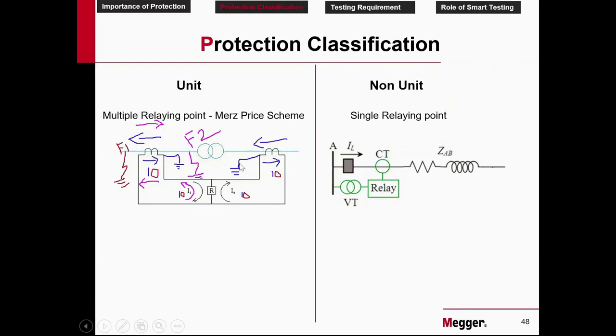Whereas here we have two CTs. This is measuring one current, this is measuring another current. We are subtracting the quantity. So we have multiple relaying points. You can have 3 CTs if it is a 3-winding transformer. You can have 10 CTs or 20 CTs if it is a bus bar. So multiple relaying points will be there. Whereas in non-unit protection, you will have only one relaying point.